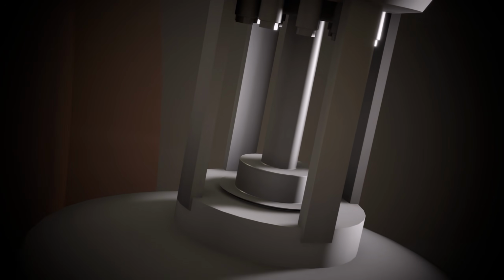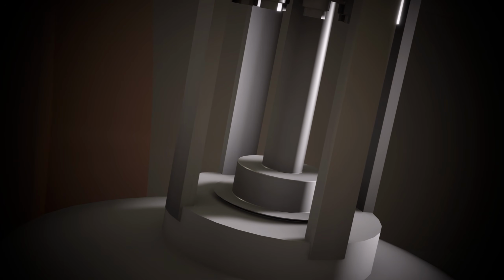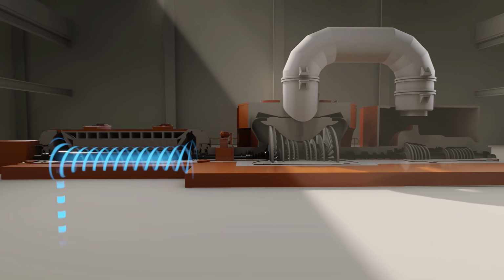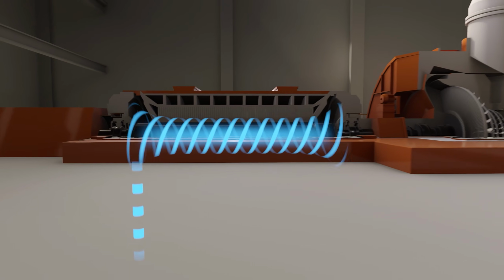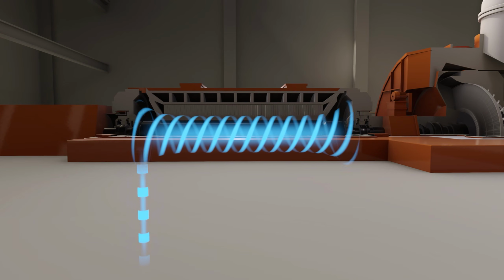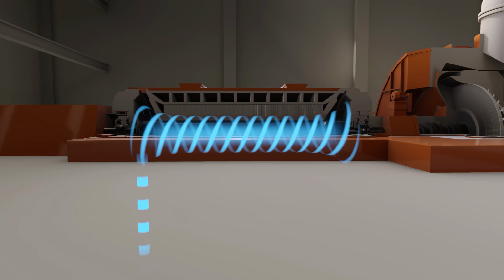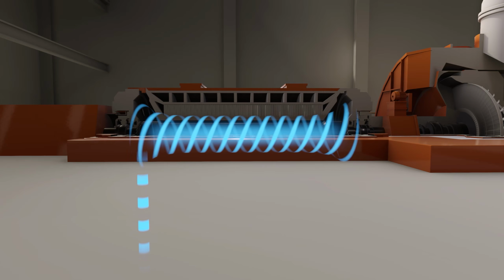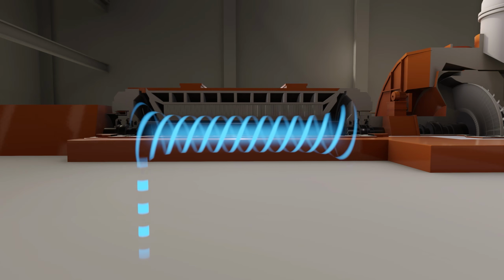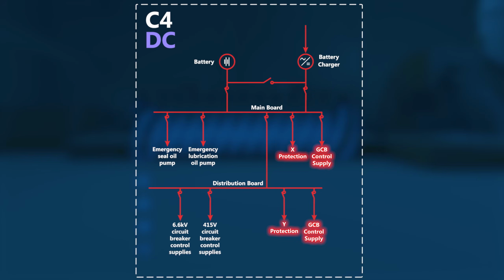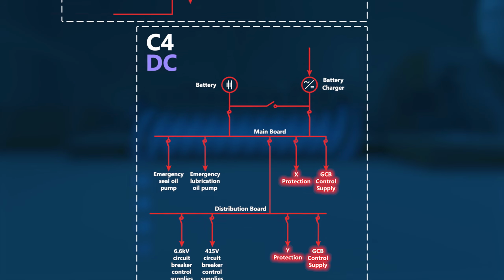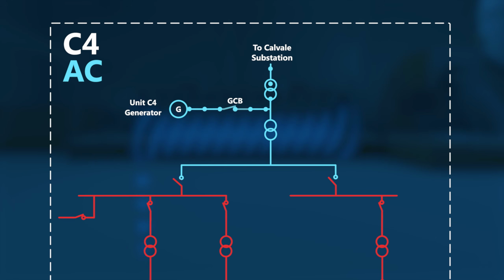As soon as AC power is lost, the steam valves slam shut. But this loss of driving power from the steam doesn't result in the turbine generator slowing down significantly. Instead, because it is still connected to the grid, the unit changes from exporting power to importing power. And as it continues to spin, with its field switch open, the generator is now an asynchronous electric motor. And the unit protections that would normally prevent this by disconnecting the unit from the grid and safely shutting it down are unavailable due to the loss of DC. This motoring of the generator will continue for the next 34 minutes.